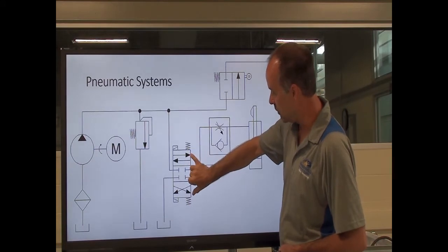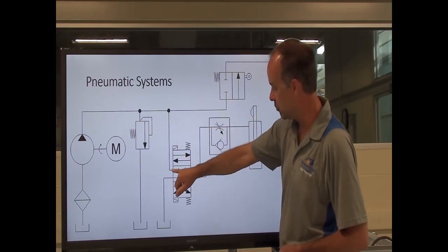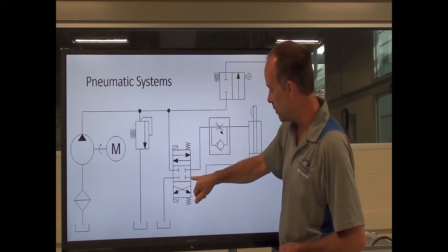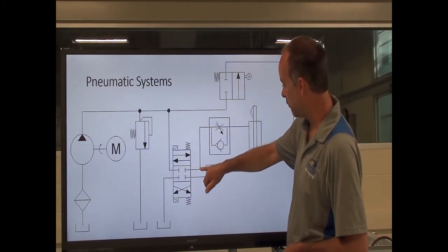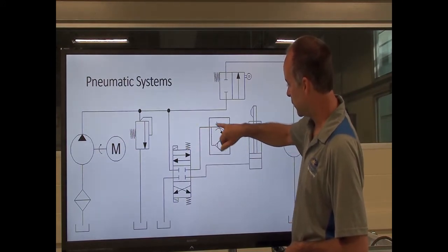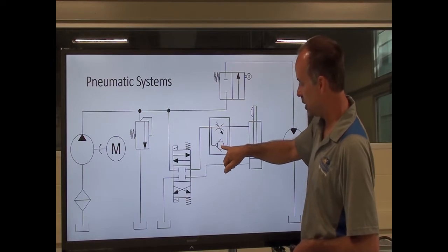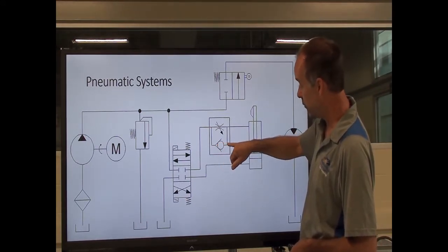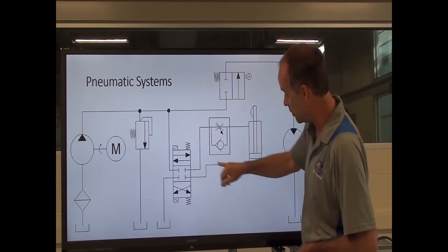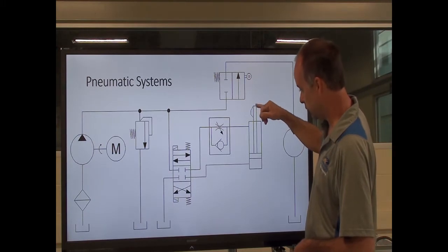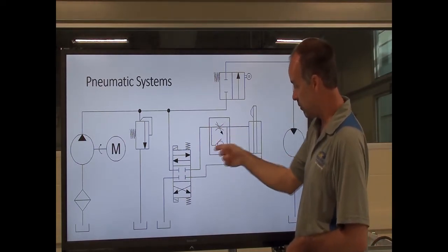Our DCV here is solenoid activated. If we energize this solenoid, we shift the valve in this direction, which is going to allow my pressure port to go to my A port and my B port draining back to tank. If I apply pressure and flow to my A port, the fluid's going to try to go through this adjustable flow control and also through this check valve. The check valve orientation allows it to open, so I'll get full flow going into this cylinder, and fluid leaving the cylinder comes back to tank. This cylinder would retract at full speed given my flow control.